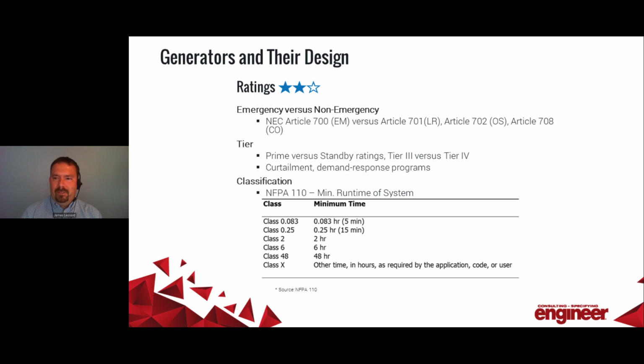So this speaks to the minimum runtime of the system. You can see the list here of the classification. So the different classifications have a different minimum runtime associated with the system. The ones we find most often are the Class 48 hours, or the Class X in a hospital setting. Generally translates to 72 hours or 96 hours. It really depends on your local authority having jurisdiction and other applicable codes.